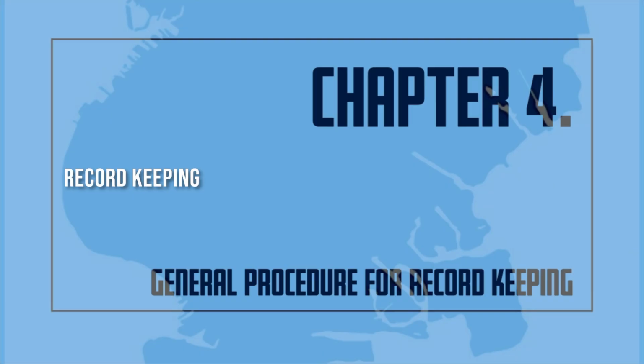Detailed records. A detailed inspection report shall include information relative to conditions of the water supply, gravity and pressure tanks and levels therein, valves, risers, piping, sprinkler heads, fire department connections, alarms, fire, booster, and special service pumps, obstructions and conditions of all other system equipment and appurtenances. All defects and/or impairments shall be noted on the report. Records shall be readily available to any representative of the fire department.